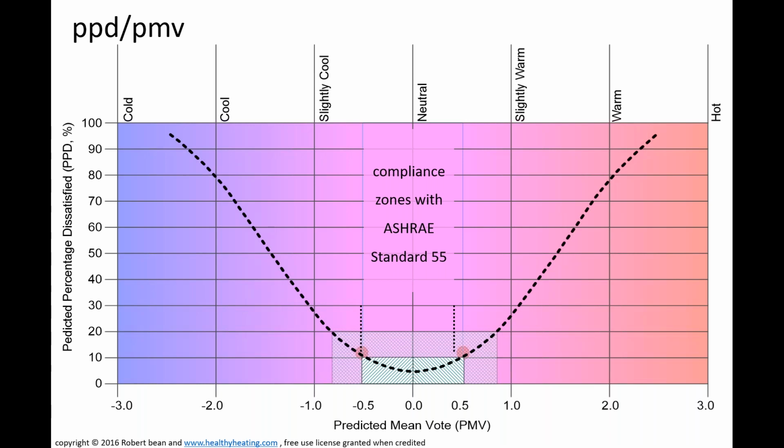And what they then did is tie the PMV to what's called the PPD, or the predicted percentage dissatisfied. And so we know that when we get everything correct, for those voting in the 0 to plus or minus 0.5, there will be a very low amount of people dissatisfied. But if we start to get any of the criteria incorrect, large mean radiant temperatures due to large window to wall ratios, poor fenestration performance, or thermal bridging in cold climates, all of these types of things, people will start to vote at a much more aggressive number. So they'll go from, say, neutral or slightly cool to cold, or up to warm or hot. And of course, these numbers then correlate to much higher numbers of dissatisfied people.